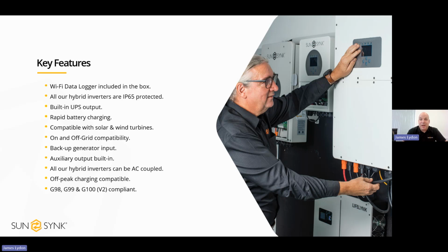If someone's completely off grid, the only thing they need to do essentially is make sure there's enough diesel in the generator, because they can set our system to say, right, okay, if the batteries get to 30% or 20% SOC, we can send that signal to the Jenny to turn on. The generator power comes into our inverter, and essentially splits two ways. It'll go one way to power the load, and the other way to charge the batteries at the same time.